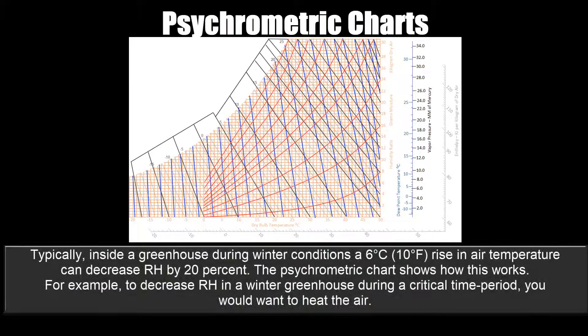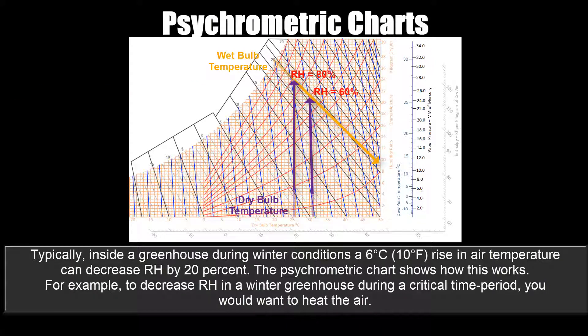Typically, inside a greenhouse during winter conditions, a 6 degree celsius or 10 degree fahrenheit rise in air temperature can decrease RH by 20%. The psychrometric chart shows how this works. For example, to decrease RH in a winter greenhouse during a critical time period, you would want to heat the air.